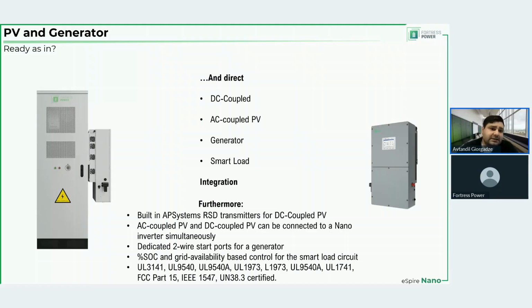Smart load, it's like load shedding, but with a single load circuit. So you can set the parameters so that the smart load is available when, let's say, the battery percentage exceeds a certain SOC, up until the point of some other SOC. Let's say you can tell it that, okay, the load circuit that is connected to the smart load port should receive power only if the battery SOC is between 40 and 60% SOC, for example.